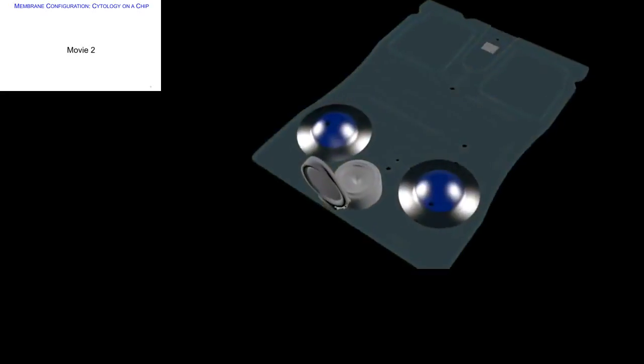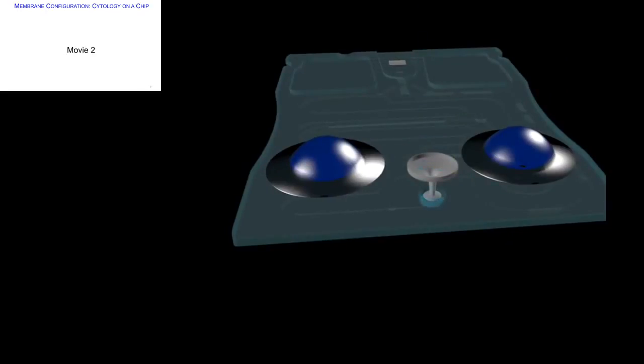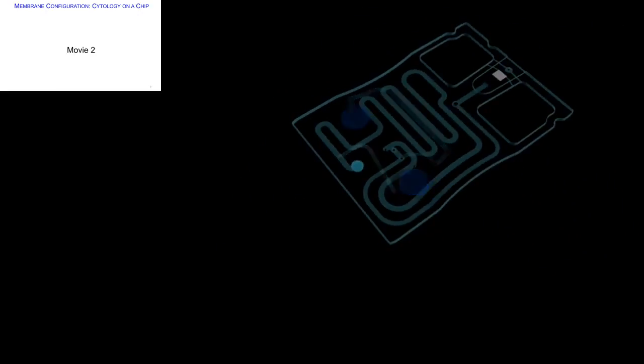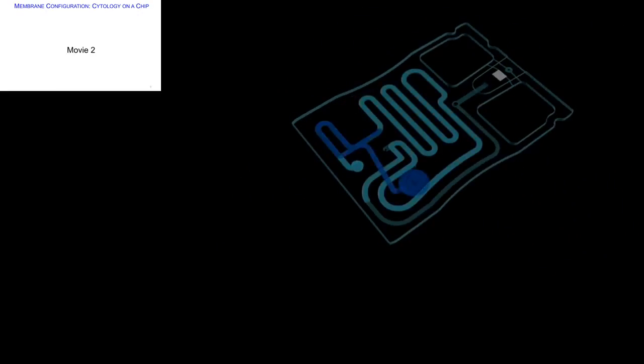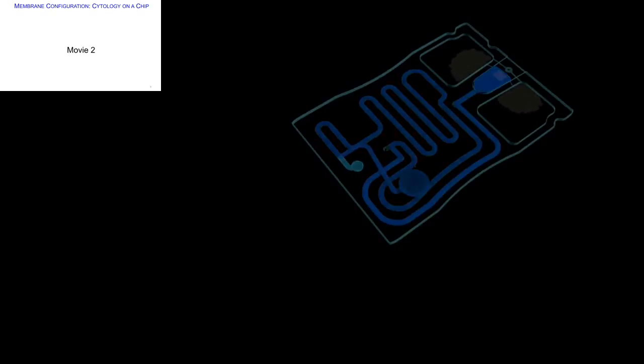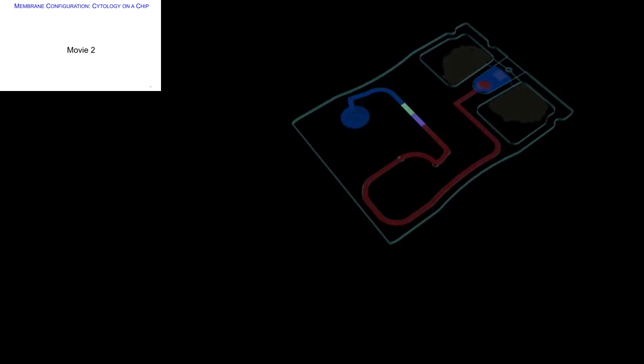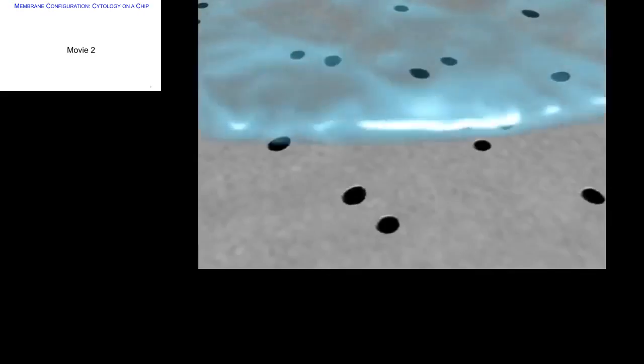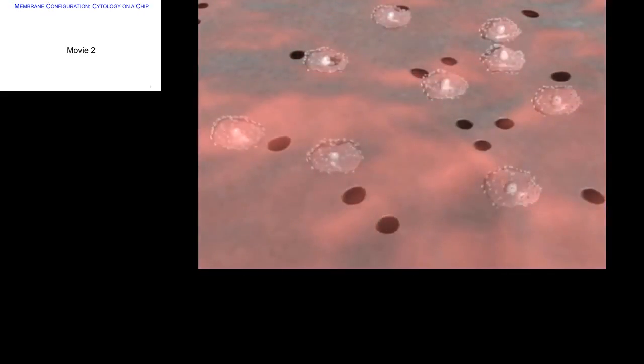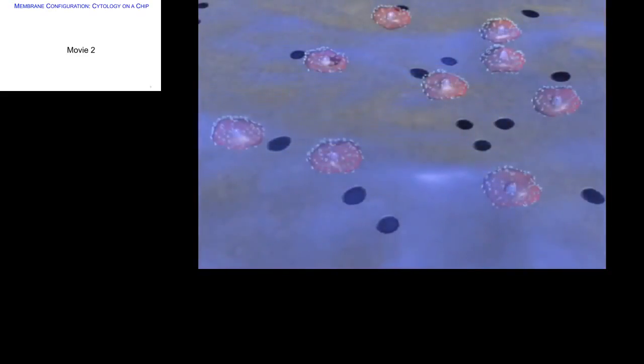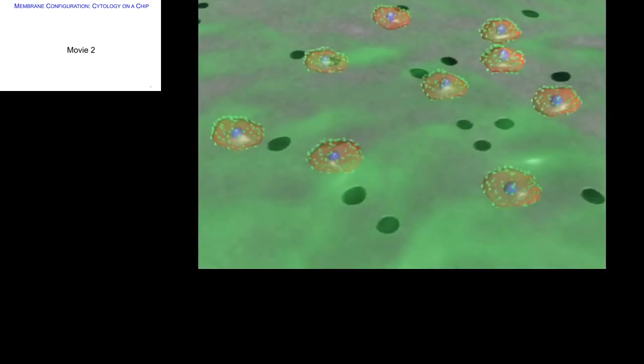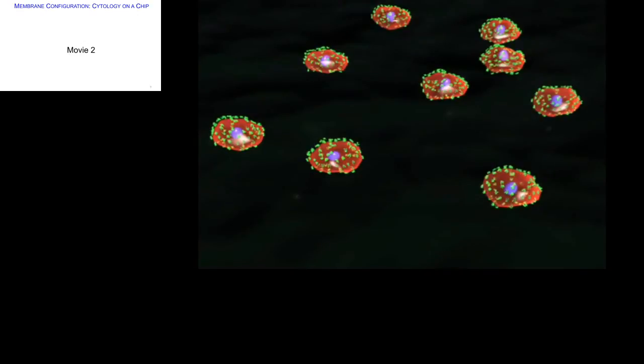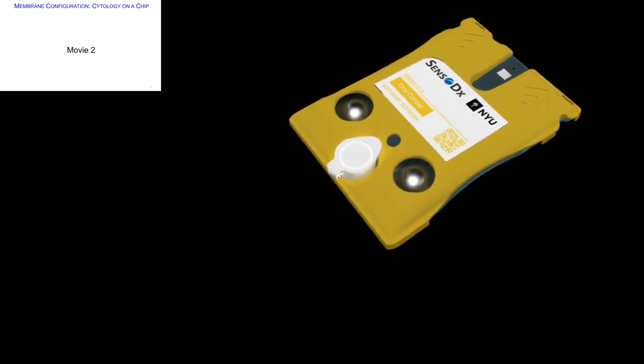Let's take a closer look at both lab card configurations, starting with the membrane-based system. A couple drops of fluid containing the cell suspension are introduced into the lab card; capillary forces draw it into the interior. The right-hand blister drives the cell suspension to the top of the card where cells are captured. The left-hand blister forces fluid through a reagent pad, redissolving red, green, and blue reagents. The reagent cocktail stains individual cells, hitting the nucleus, cytoplasm, and various surface markers. Using this process, high-content single-cell analysis is completed at the point of care.